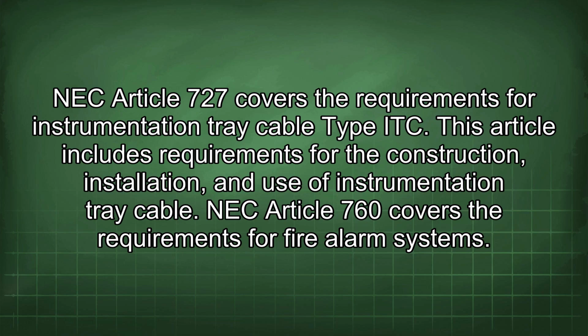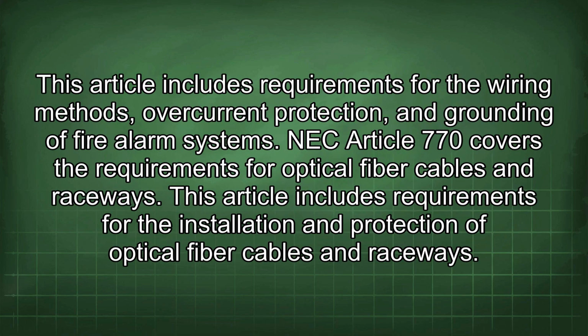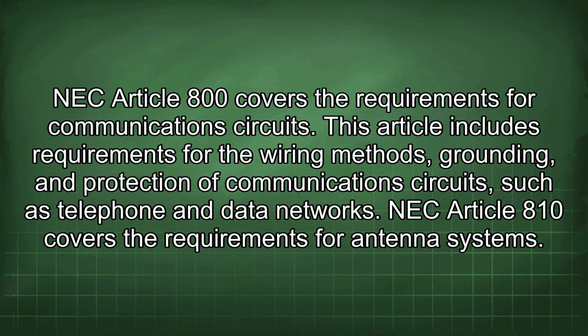NEC Article 760 covers the requirements for fire alarm systems. This article includes requirements for the wiring methods, overcurrent protection, and grounding of fire alarm systems. NEC Article 770 covers the requirements for optical fiber cables and raceways. This article includes requirements for the installation and protection of optical fiber cables and raceways. NEC Article 800 covers the requirements for communications circuits. This article includes requirements for the wiring methods, grounding, and protection of communications circuits such as telephone and data networks.